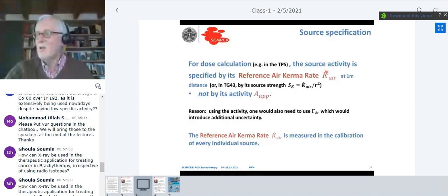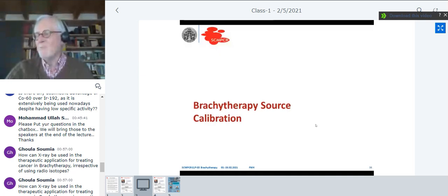We directly use the air kerma rate. This is something that can be measured, and that is the way sources are actually calibrated, by measuring the air kerma rate. That will be the content of the next slides that I will show you tomorrow, brachytherapy source calibration.